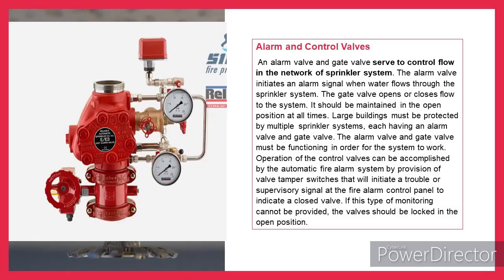Alarm and control valves. An alarm valve and gate valve are important. It serves to control flow in the network of sprinkler system. The alarm valve initiates an alarm signal when water flows through the sprinkler system. The gate valve opens or closes flow to the system. It should be maintained in the open position at all times.